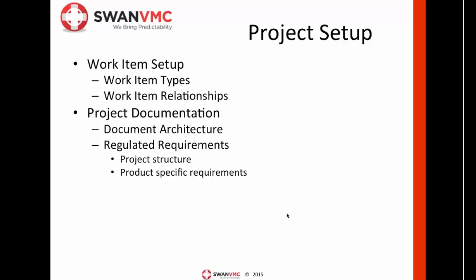In this phase, we also discuss the regulatory requirements of the project. Every medical project has certain required components, and the company will need to decide what component goes where in the document set. So for example, every project will require a project plan, a risk management plan, a risk management analysis, and a risk management report, and input definition, just to name a few. But also each product has its unique set of requirements because the device is inherently different. And so, for example, some have software and some don't. And oftentimes, particular devices, of course, have their own regulatory documents that are associated with them.